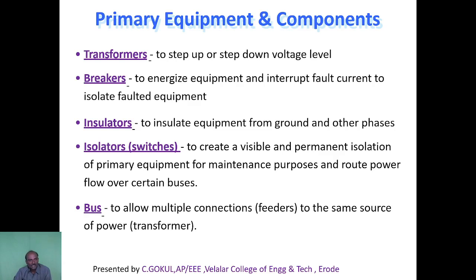Then primary equipments to be protected, transformers, we have step up and step down transformers, breakers. So what's the importance of the breakers? It is to energize the equipment and interrupt fault current to isolate the faulted equipment. So with the breaker use only, we can isolate the faulted equipment. Insulators. It is to insulate the equipment from ground and other phases. Isolators, normally the switches. It is creating visible and permanent isolation of primary equipment for maintenance purposes.